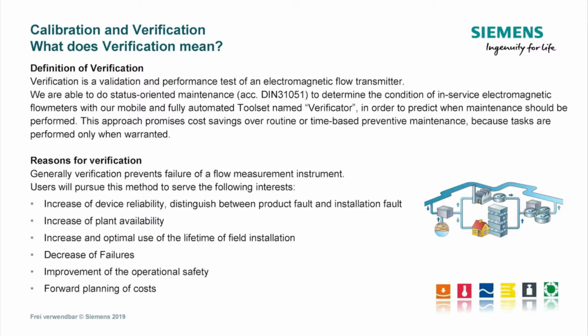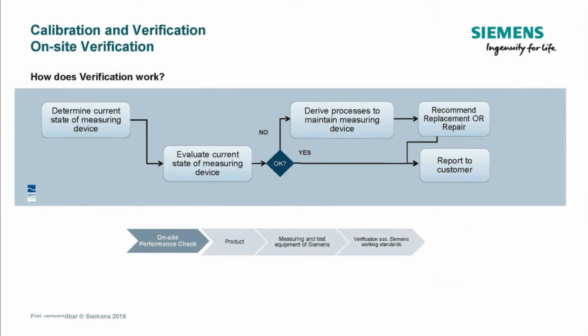Reasons for verification. Generally, verification prevents failure of a flow measurement instrument. Users will pursue this method to serve the following interests: increase of device reliability, distinguishing between product fault and installation fault, increase of plant availability, increase and optimal use of the lifetime of field installation, decrease of failures, improvement of operational safety, and forward planning of costs. Here is a flow diagram of the Siemens on-site verification process.